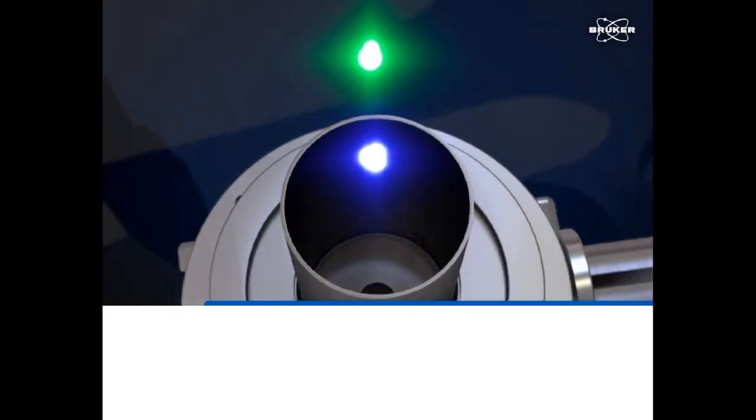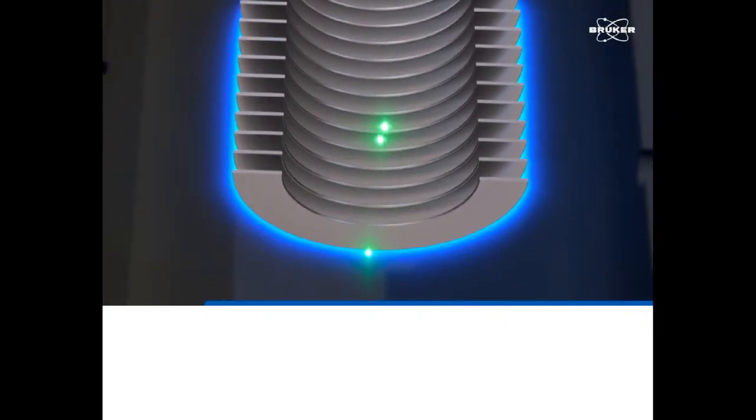In this process, precursor ions and their respective fragments travel together at the same speed. Based on the expected time of flight of the precursor ions, specific ion packages may be individually selected, and all other ions blocked from continuing through the flight tube. The selected ions are then re-accelerated, with the precursor and fragment ions traveling at different speeds towards the reflector detector. The ions travel via the reflector towards the detector, and thus a TOF spectrum is recorded.